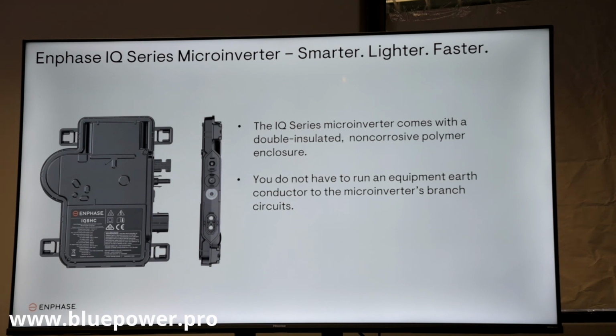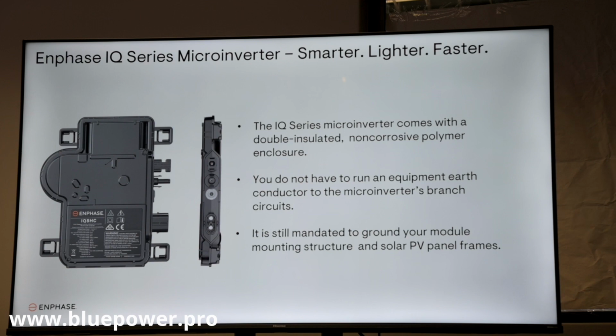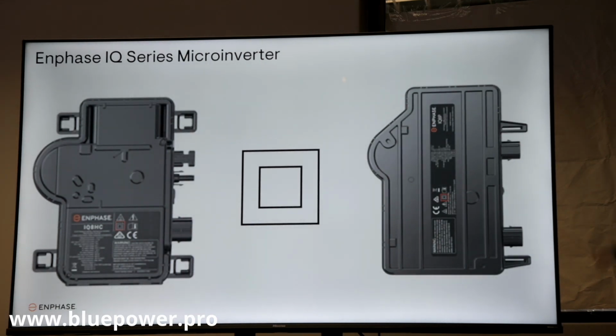So you do not run an equipment earth conductor to the microinverter's branch circuits. That cuts down also on expenses, because copper wire is expensive. But as I said, it's still mandated that your rail system must be grounded, must have an earth spike in, etc. So if you have a look on those microinverters, you'll see the symbol for double insulated. This is on all our microinverter products.